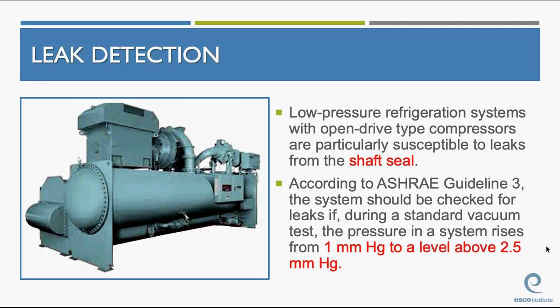Low pressure refrigeration systems with open drive type compressors, you got to check the shaft seal. This is an open drive. I have a motor that's here, and I have a connection to the compressor with a drive. I showed you this on another picture earlier. Open drive compressors leak around the shaft seals.